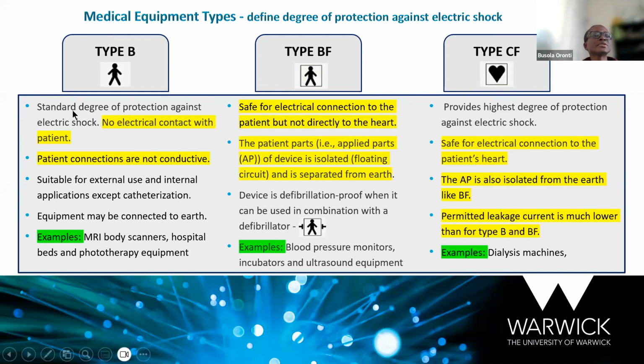Now, if you look at the first one, it's saying that you will class a medical device as a type B, whether it is class 1, class 2, or class 3, if there is no electrical contact with the patient. And whatever connection you have with the patient from that equipment is not conductive. So that's what it means. And examples are MRI, body scanners, hospital beds, phototherapy equipment.